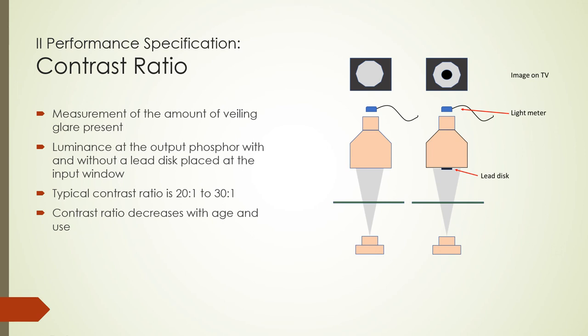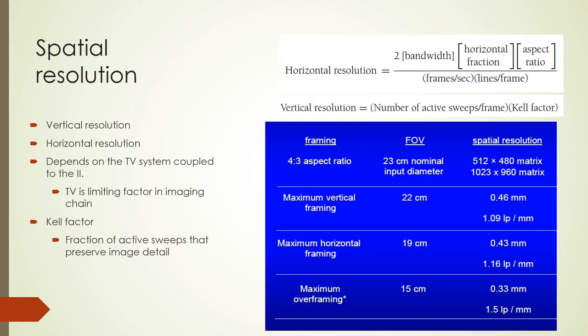In a fluoroscopy system based on an image intensifier and a TV camera, spatial resolution can be separated into vertical and horizontal components. Vertical resolution is the number of active sweeps per frame multiplied by the Kell factor — a fraction of active sweeps effective in preserving detail. Active sweeps are about 93 percent of the possible lines. Horizontal resolution has additional factors. The overall spatial resolution of the imaging system is limited by the capabilities of the TV system coupled to the image intensifier. A table shows what spatial resolution can be expected for a given field of view.